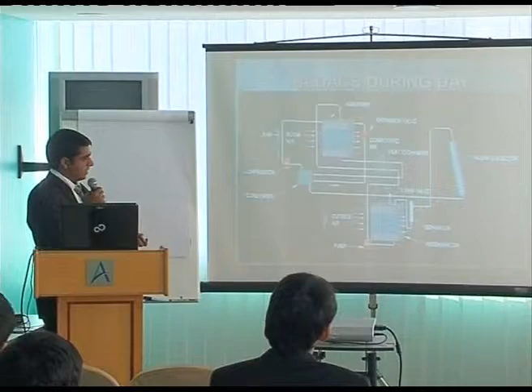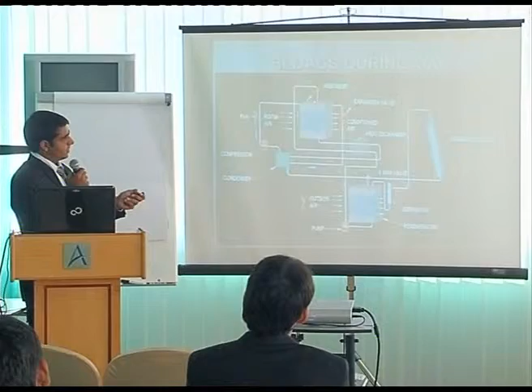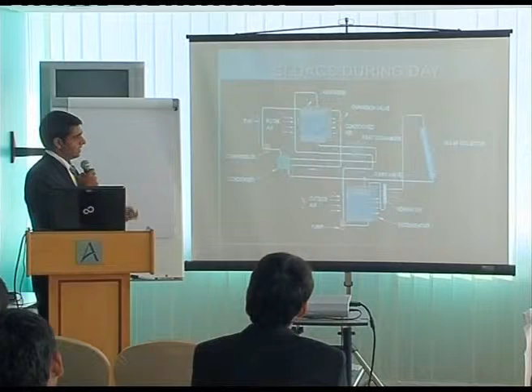Here the pressure of the liquid desiccant will be more than the outside air, so it will directly give out the moisture. So now what happens? The liquid content will reduce in the liquid desiccant, the concentration of desiccant will increase, and we will get a strong liquid desiccant solution. This strong liquid desiccant solution is then again pumped back to the heat exchanger, where it will reject some heat to the weak liquid desiccant solution, and then it is further moved to the absorber, and the process will repeat again. In this way the cycle repeats. So that's the solar liquid desiccant air conditioning system during the daytime.